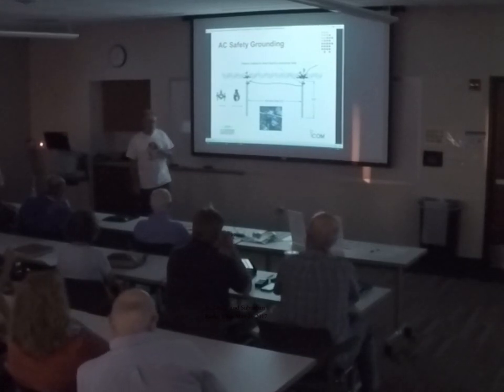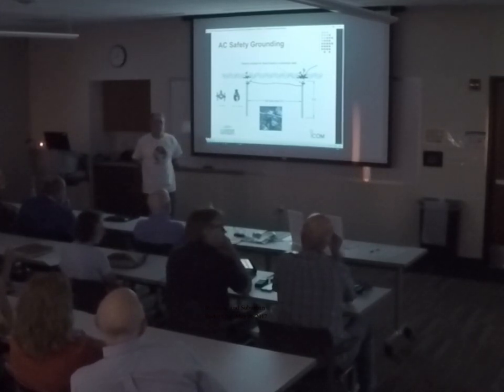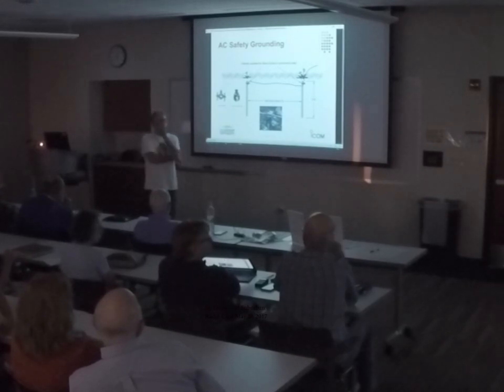Or we'll be reading about you. That's right. I'm in the county now, mine was all inspected when they did it, in the early 2000s. It's got a solid copper wire that runs from the meter on the outside of the building to the ground rod right there in the ground. But then from the ground bus, it runs up to the cold water pipe in the front, and it is metal all the way. I'm confused why they have that ground rod, but they didn't actually bond to that ground rod from the panel.